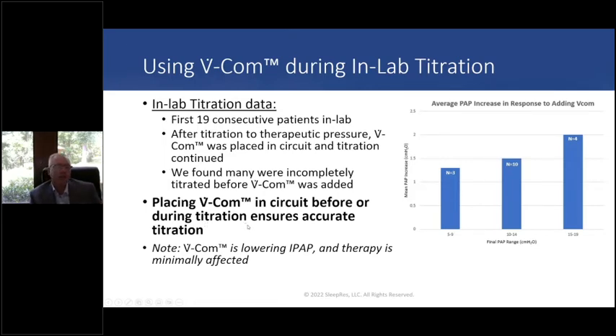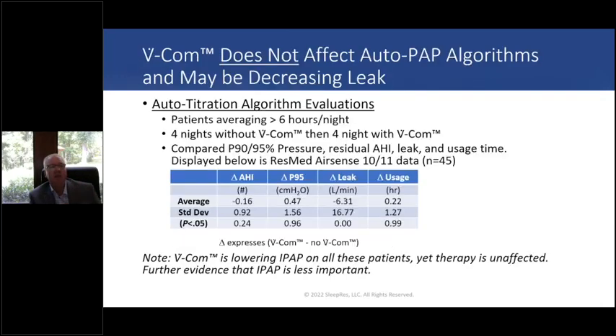And of course the other thing this shows, and all the VCOM data shows, is that VCOM is lowering IPAP. I mean, it might be lowering EPAP a little bit here, but it's really lowering IPAP, and the therapy is minimally affected. Now, does VCOM affect auto algorithms? Well, not that we can find. And it may actually be improving therapy by decreasing the leak.